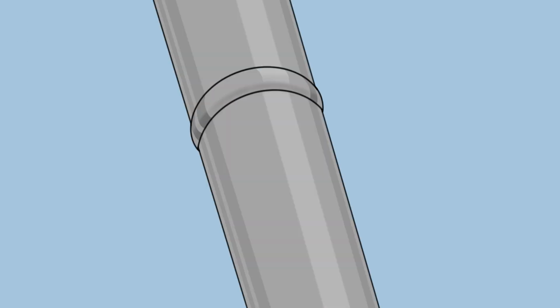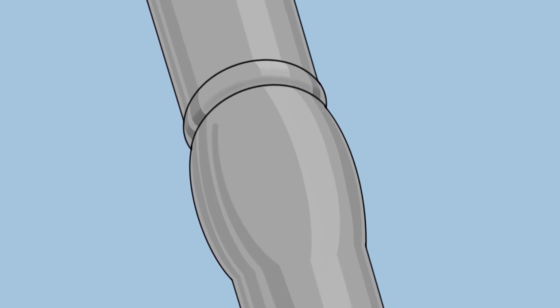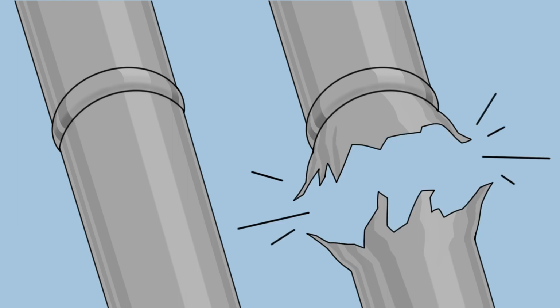It is also very important to understand that existing exhaust ductwork should never be pressurized by a HEPA-filtered fan or negative air machine. The building's exhaust ductwork was constructed to operate under low pressure from a fan that pulls air into it. The ductwork used for fans that supply or push air through the ductwork has more stringent construction requirements to ensure it can withstand the higher static pressure.